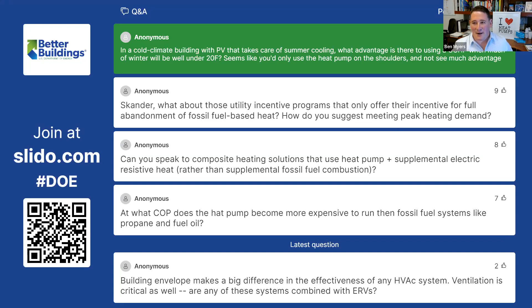If I can add to that, Ben, I think we have a particular client where we're doing a similar type of air source heat pump, more of what I consider a 4-pipe traditional VAV system applied with an air source chiller heater unit. There is a concern about those low temps. So I think each case has to be thought about uniquely with the owner, understanding their concerns, and then as an engineer, how do you address those concerns with redundancy and resiliency.